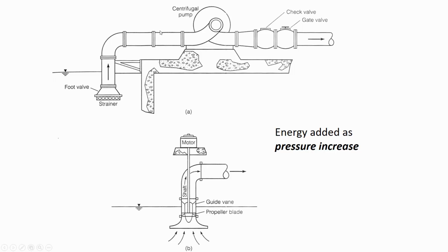So the point I'm making is that as the water is flowing through the suction side of the pump, the pressure is decreasing. One of the things we have to be cautious about when we're placing a pump is that we don't want to have the pump too far away from the water source. It's okay if you have a really long run of pipe after the pump, but before the pump, you have to be careful about having too long of a run of pipe because you may have cavitation.